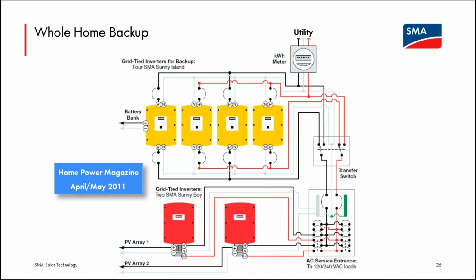For 6,000 watt Sunny Islands, their actual full, the 3-hour rating is 6,000 watts. The full continuous rating is 5,750 watts. 4 of those running continuously is 23,000 watts of just battery power. 23,000 watts is close to 100 amps continuous on a 240 volt panel. That really is truly getting close to whole home backup. Most homes don't pull 100 amps from the utility grid.